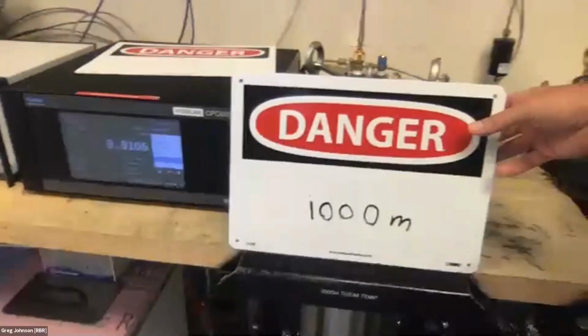The test is finished. It's not actually at 1000 dbar anymore. And the reason we do a double calibration at both room temperature and about 4 degrees Celsius on our cold tank, and then also a full temperature calibration of every pressure sensor from -5 to 35, is that most pressure gauges are exceptional thermometers, and pressure is almost a secondary measurement to them. So you need to get rid of all the temperature effects first.